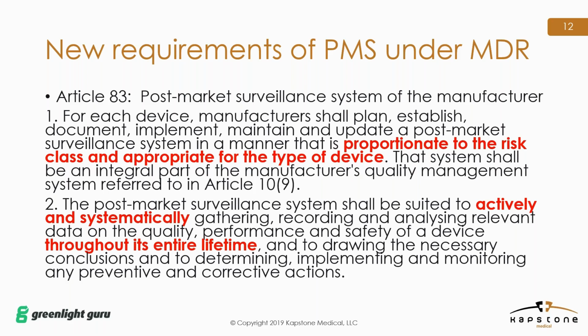We've already touched previously on what an active and systematic approach to PMS is. So lastly, lifetime. This is intended to highlight the requirement for considering performance and safety of the device throughout the claimed lifetime of the device based on its clinical application. So it's not shelf life, it's not just until you sell it to the customer. It needs to be considered throughout the entire lifetime of that device. So at this point, I think you're starting to see the general intent of the requirements. There's an organizational requirement to have an active role in maintaining the safety and performance of the device and consider it for the lifetime of the device.